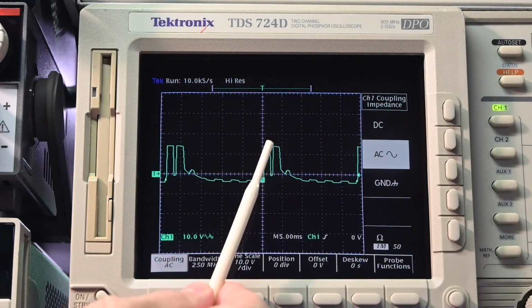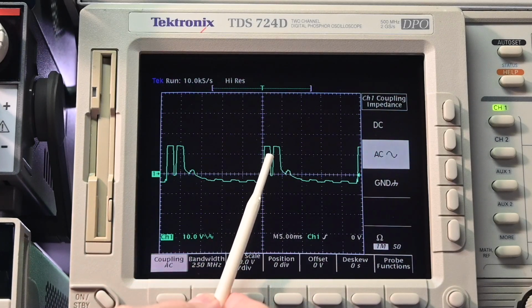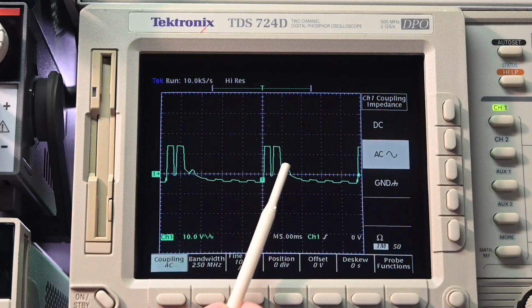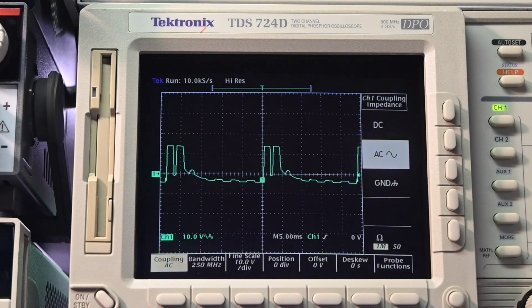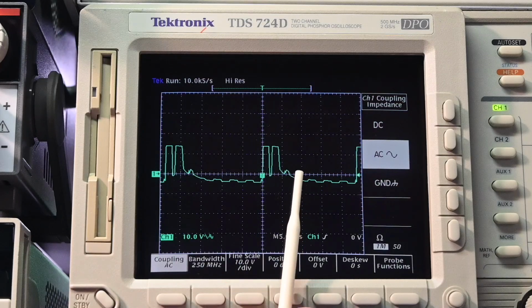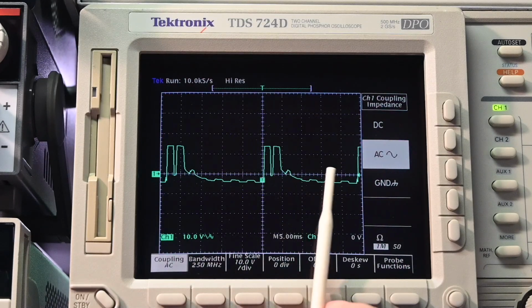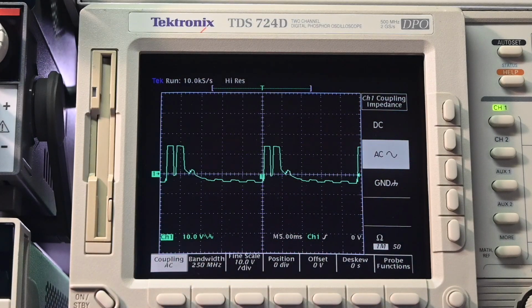And on the trailing edge, there's an extra pulse as it's dropping down right there. Almost looks like some noise or something going on. And the service manual mentions that if that occurs, it can be a sign of an oscillation. So that shouldn't be there. Now, on this trailing edge, as it drops down, and then you have 3 more pulses that are very small, that's normal. Those should be there.